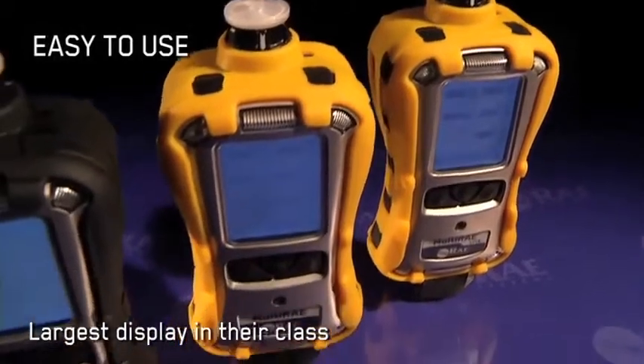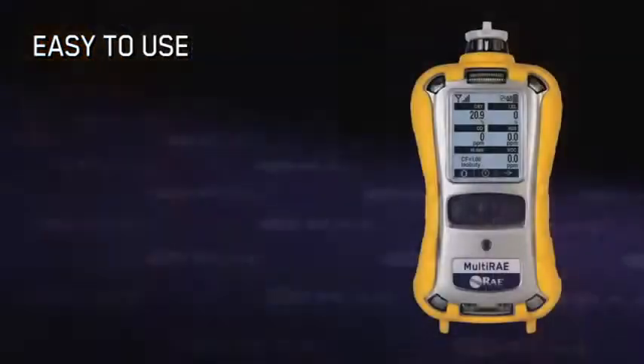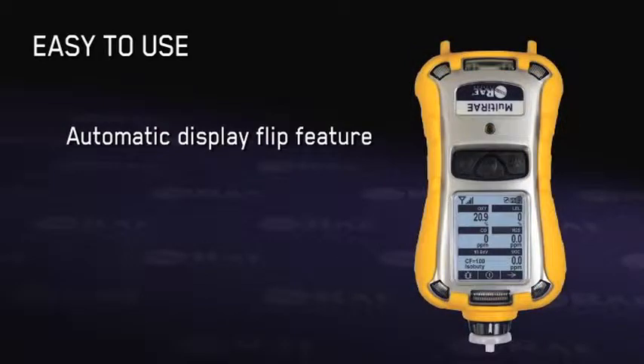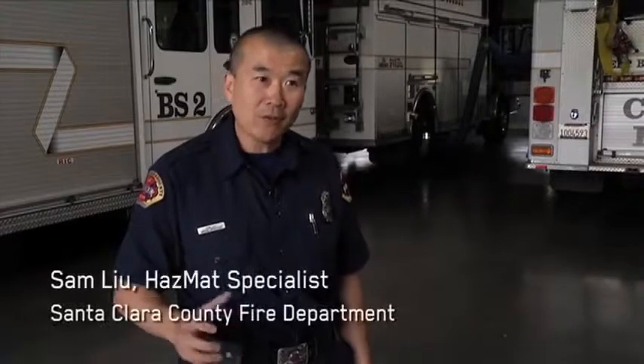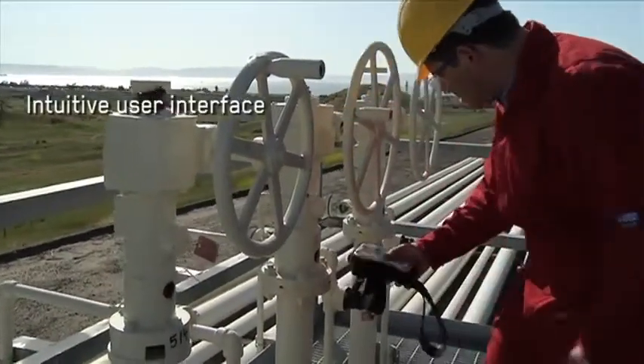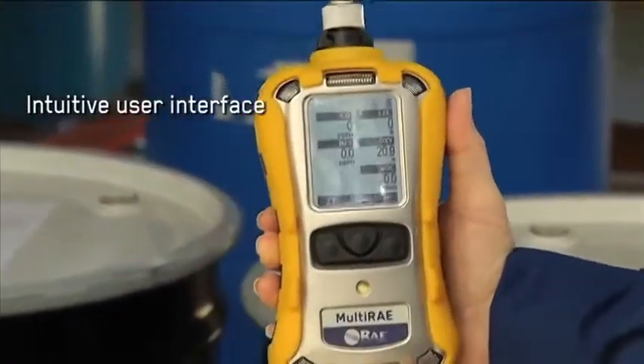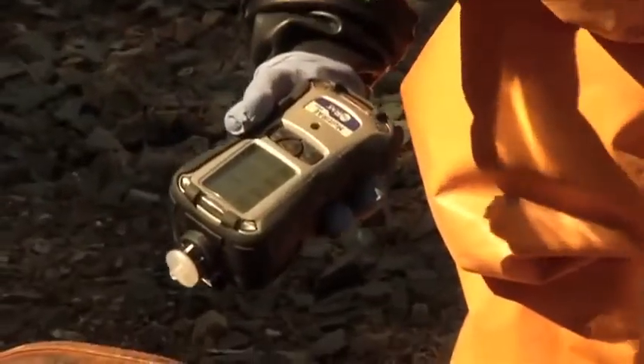Boasting the largest display in their class, the MultiRAE monitors are extremely easy to operate. Their unique automatic display flip feature enables convenient readings of gas concentrations when the instrument is used or carried upside down. The motion feature flips the screen when you flip the instrument, so you don't have to press a button. The MultiRAE's familiar intuitive user interface puts all the critical readouts at the user's fingertips. The instrument's ergonomically contoured shape is comfortable to grasp and hold, and its large buttons are usable in three layers of gloves.